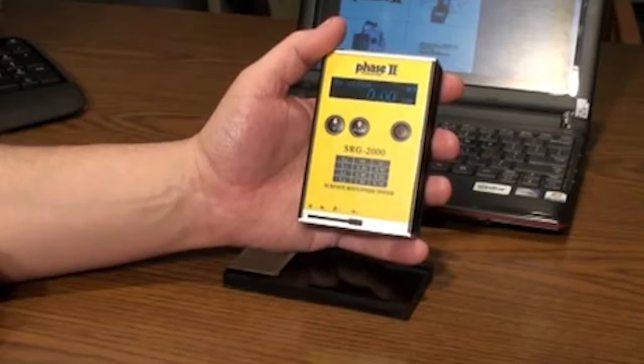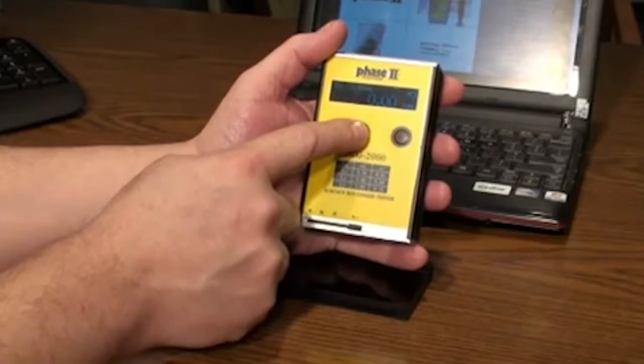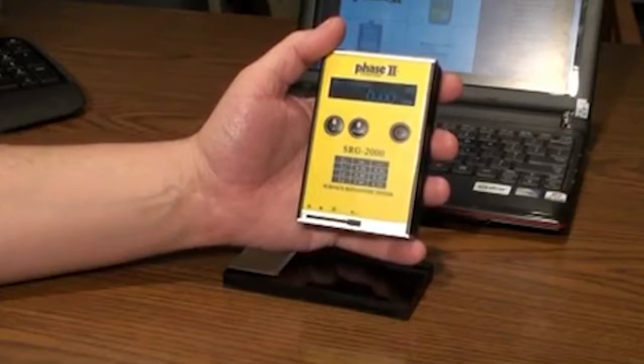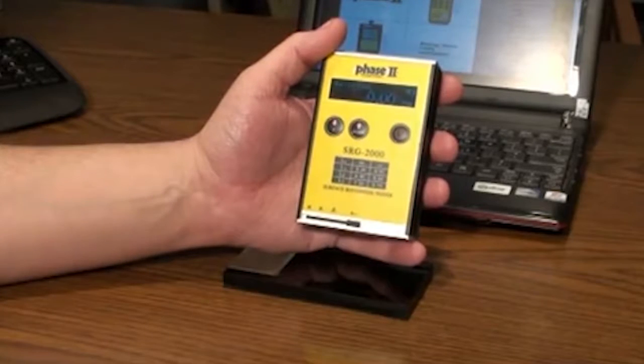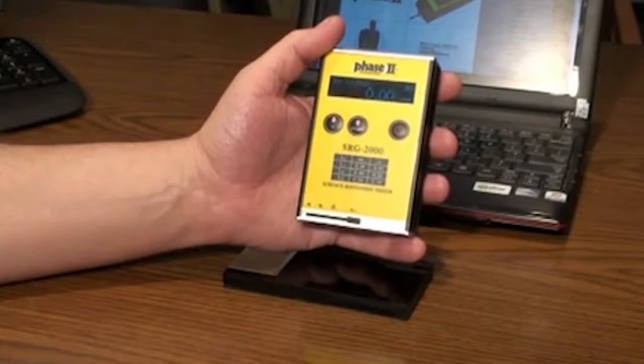The very same button will allow you to select the correct cutoff length. This represents the sampling length of the test. The correct value is determined by approximate surface roughness. This can be referenced in a chart in the operation manual showing various ranges.